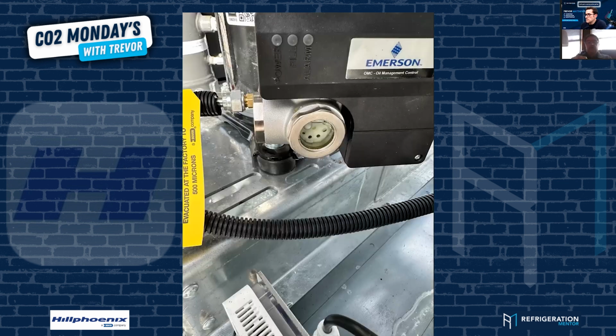All right, back one more. Back. Hit oil. The other thing you need to look at if you're not transferring oil to your medium temp compressors is what is your vessel pressure, graph your vessel pressure, graph your suction pressure. You need a minimum of 65 PSI to push oil on a differential through that solenoid. Some people say minimum, they want to see 80. I want to see 100 because there's too many times where the suction and the vessel will modulate to each other. And if they sit there too much and you call for oil, you're not going to transfer. Or you're going to transfer slow. So look at that also.